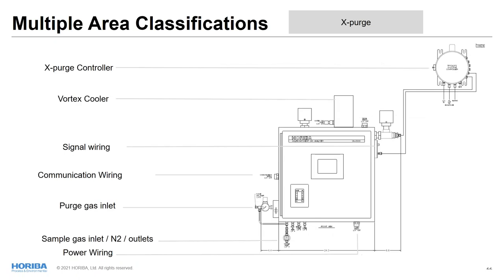The X-purge version is the system which controls the pressure and turns electricity on and off. The system is watching the pressure inside of the cabinet. When you lose the pressure inside, the system shuts down the whole power supply so that no electricity will touch the flammable gas, which prevents the explosion or risk of explosion. So that's the X-purge version.